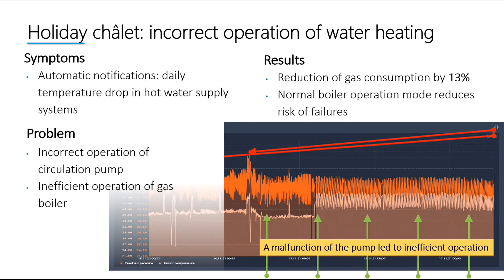Once this circulation pump was fixed, first of all the gas consumption was reduced. Instead of these high peaks, there's now normal operation of the gas boiler, and also a reduction of wasted water that was dumped from the heating system, and obviously less risk for operation of the boiler.